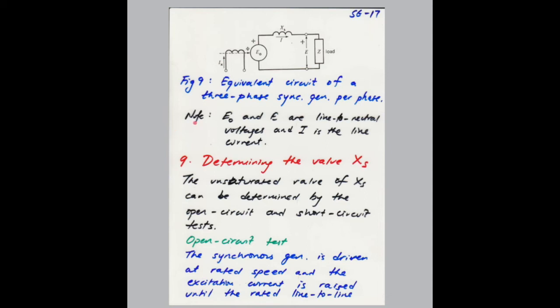Now, this circuit is basically showing you the effect of the rotor, which is carrying the rotor excitation current, Ix, producing the flux, and that's basically determining the value of E naught, which is the induced voltage per phase. In between the load and this induced voltage, you will have the synchronous reactance, which represents the reactance of the stator per phase, right? And the current that's passing here will be your load current. The terminal voltage, known as E, is basically the voltage between terminal line to the neutral, right? So these parameters, you need to know them, you need to be very precise.